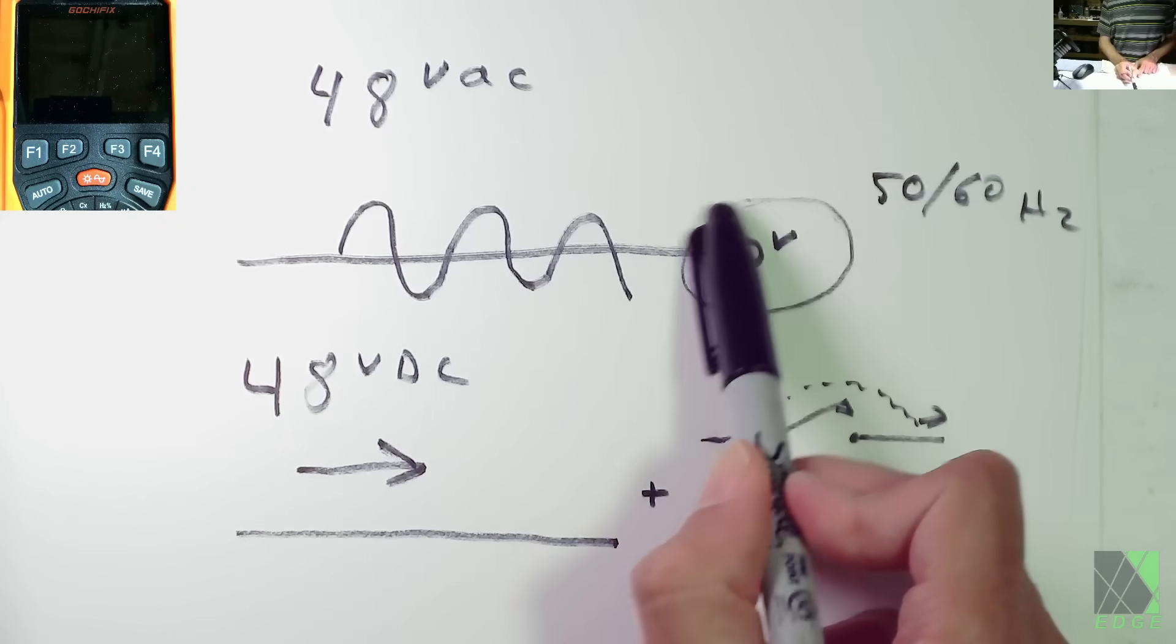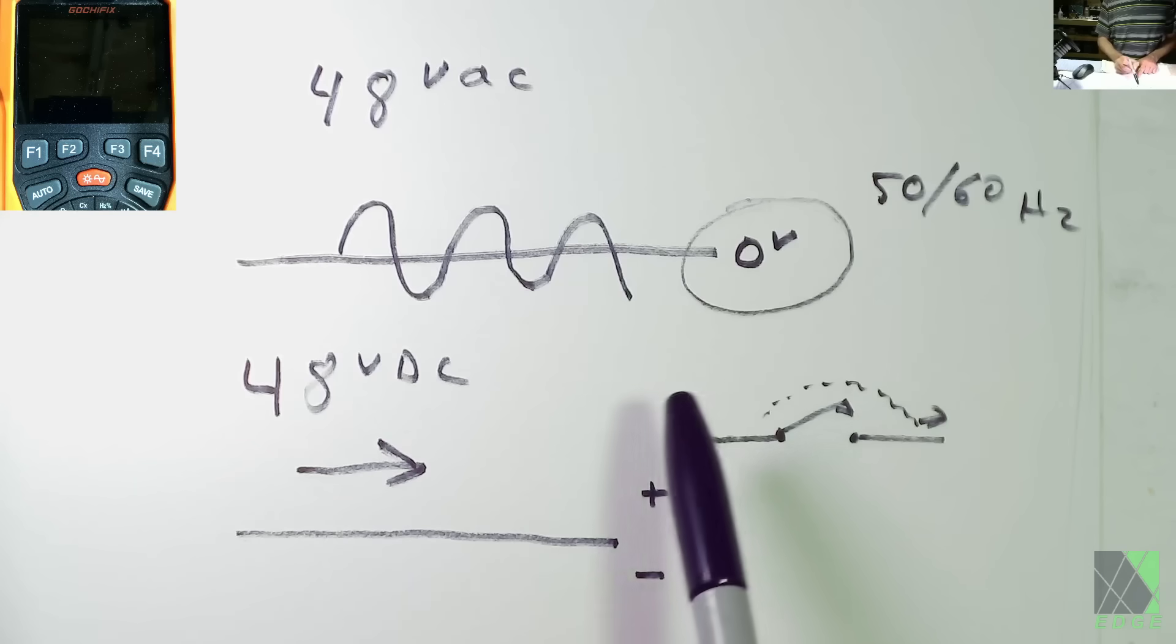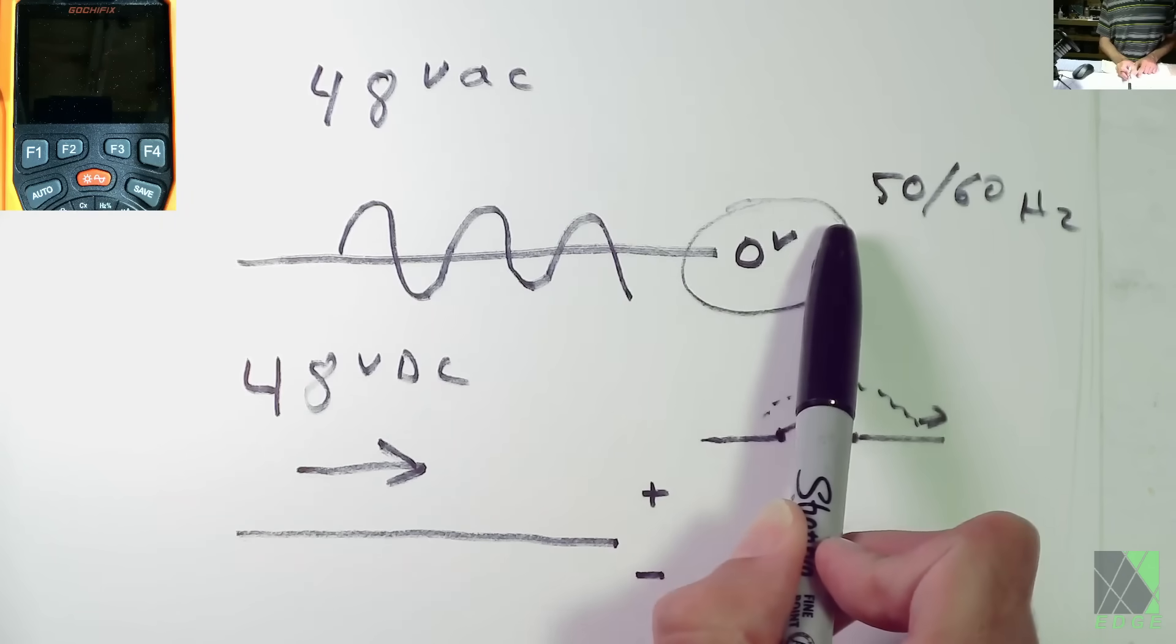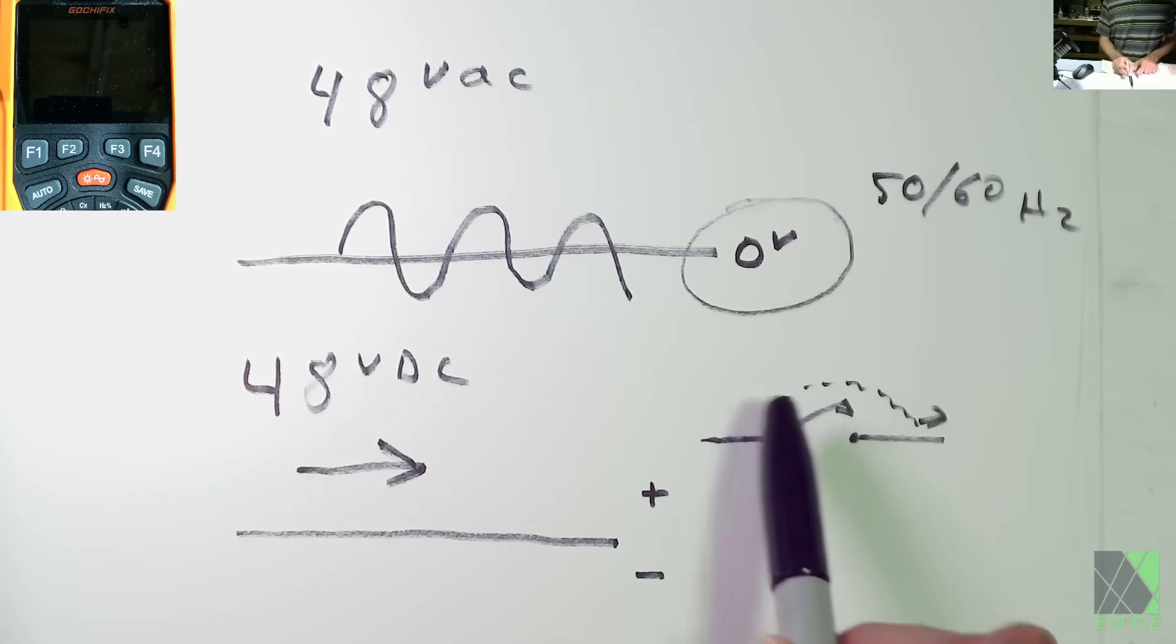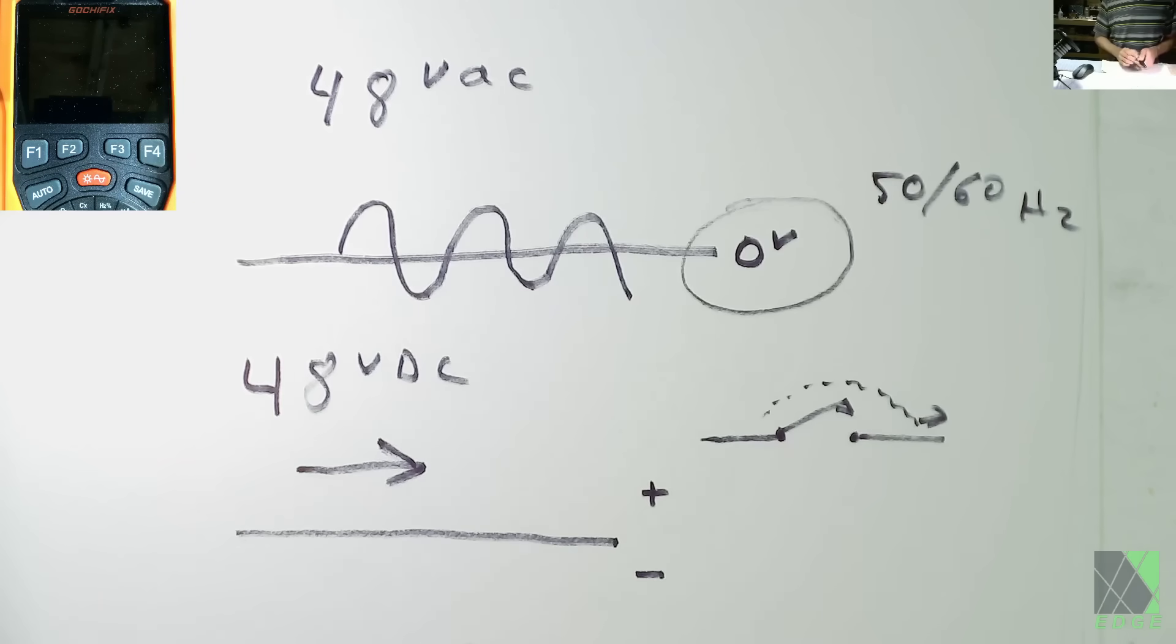But clearly at some point this AC is going to be at zero volts. That's going to help interrupt the arc. And because of this zero volts here, that means that AC, it does arc, but it doesn't behave the same as DC. DC doesn't alternate. And so when you open a gap like this, it's going to want to keep going. And because of that, you have to have a way to suppress and extinguish any DC arcs that take place.